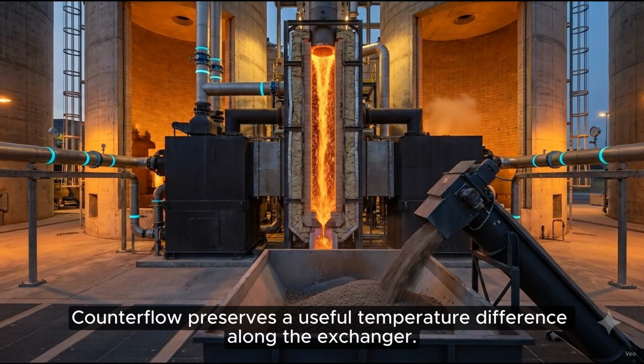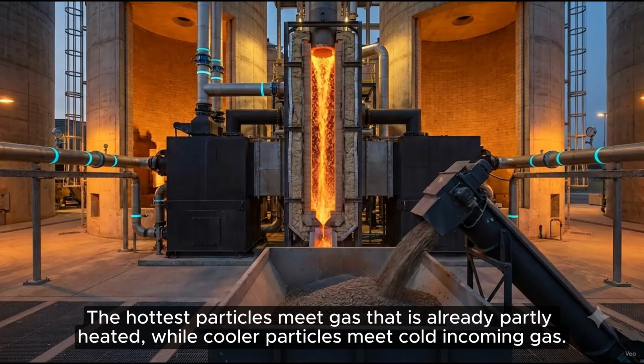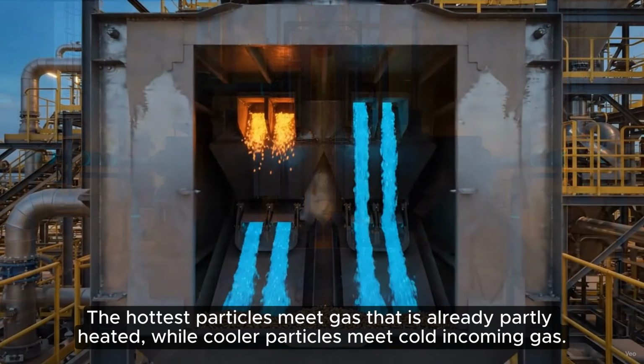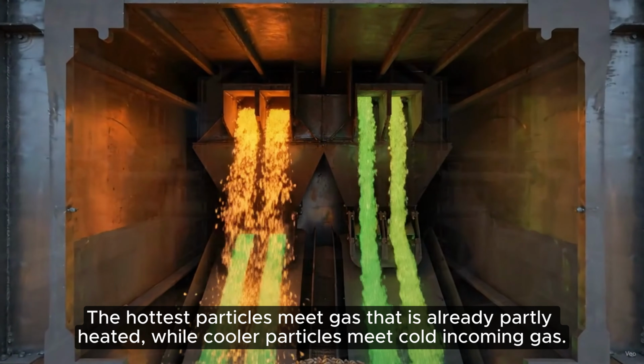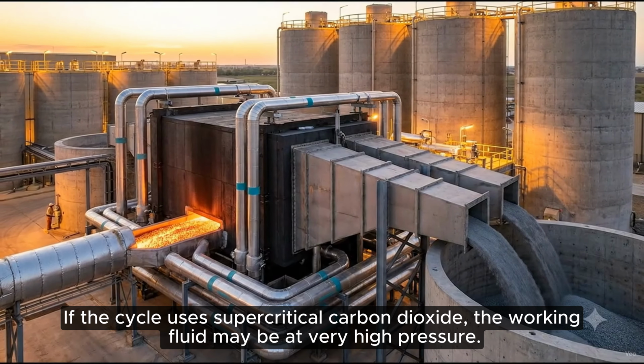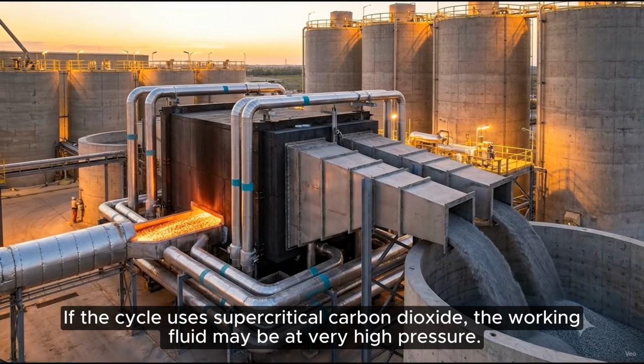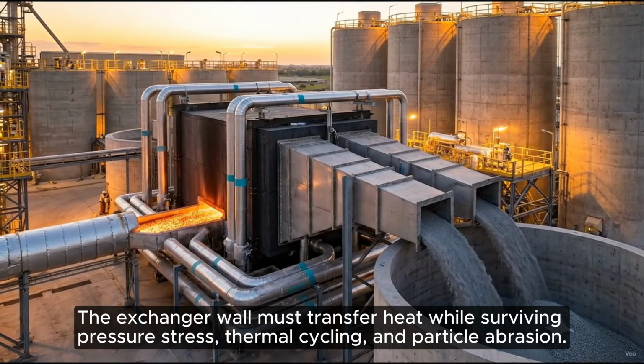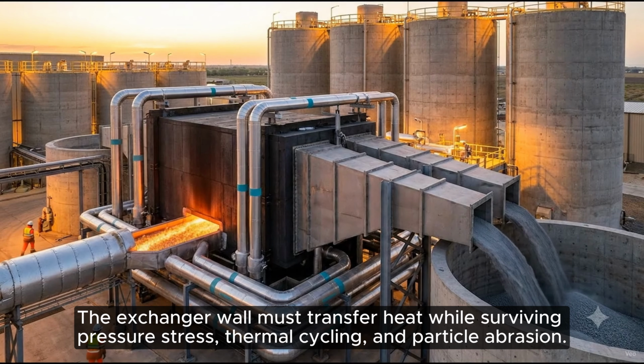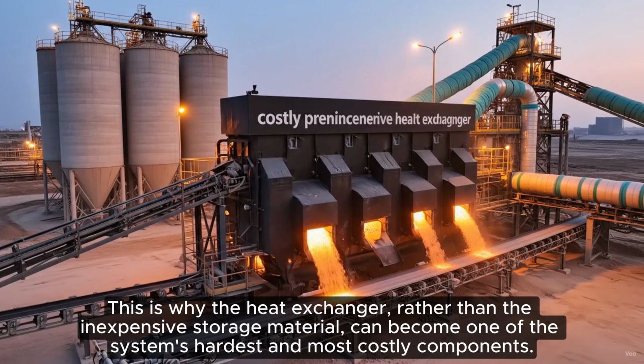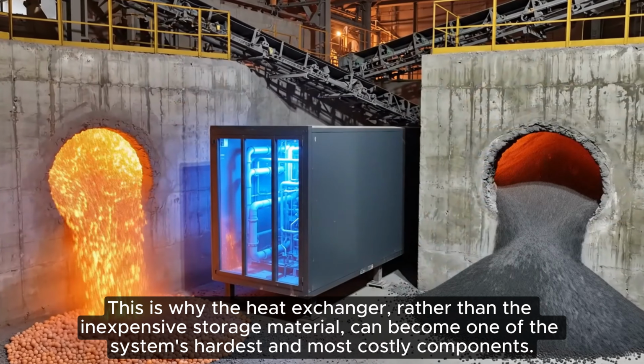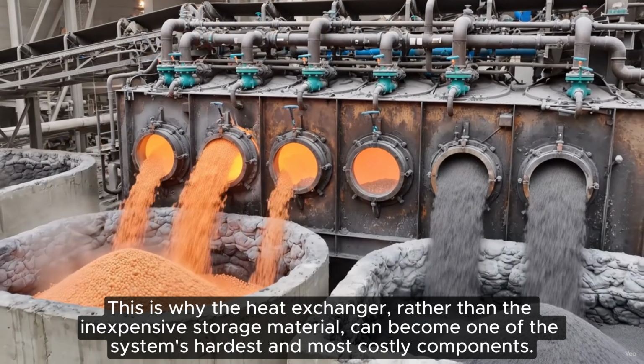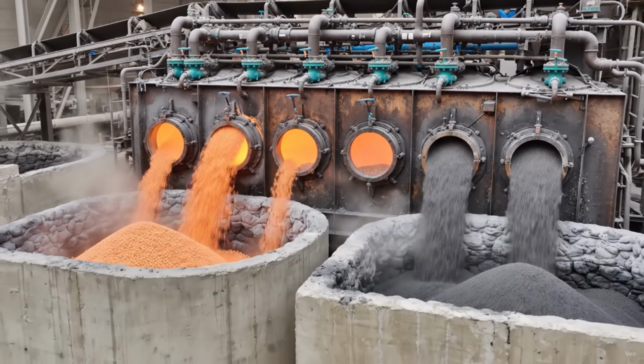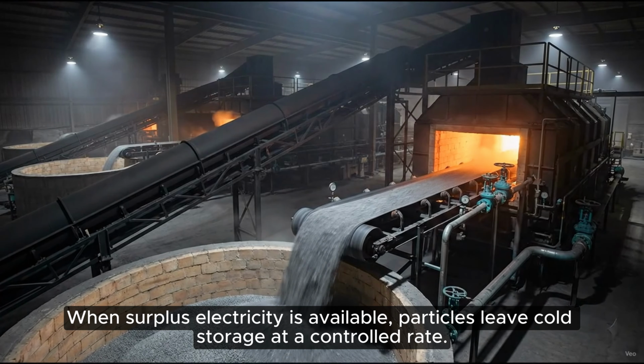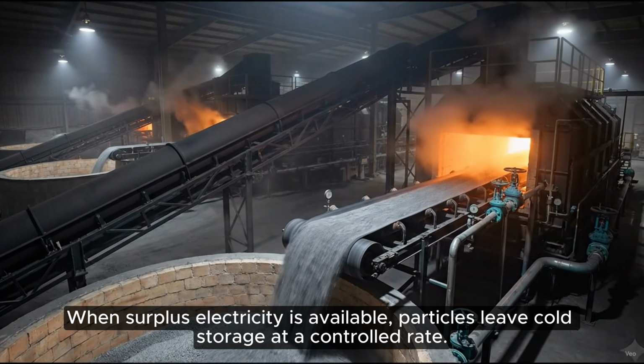Counterflow preserves a useful temperature difference along the exchanger. The hottest particles meet gas that is already partly heated, while cooler particles meet cold incoming gas. If the cycle uses supercritical carbon dioxide, the working fluid may be at very high pressure. The exchanger wall must transfer heat while surviving pressure stress, thermal cycling, and particle abrasion. This is why the heat exchanger, rather than the inexpensive storage material, can become one of the system's hardest and most costly components.